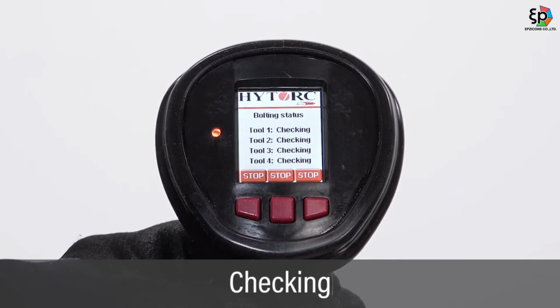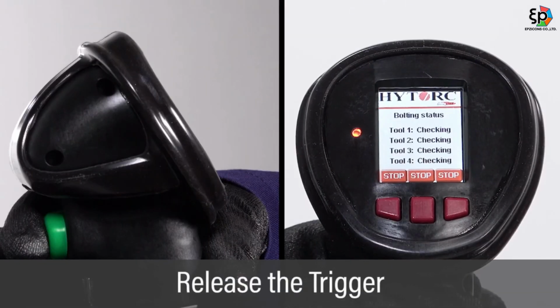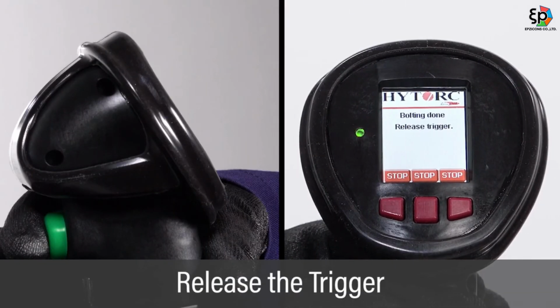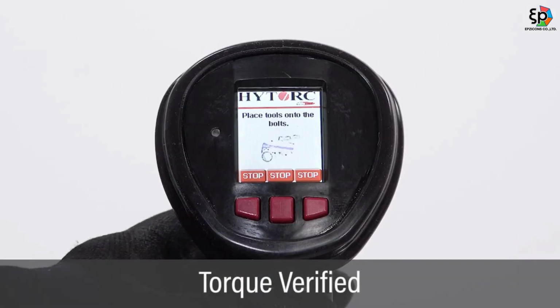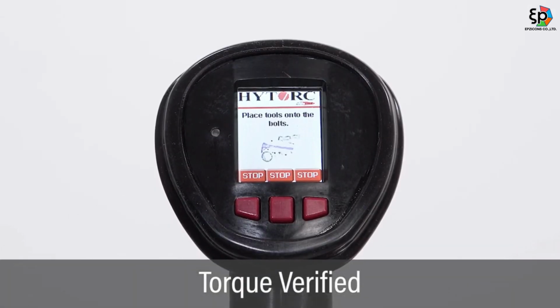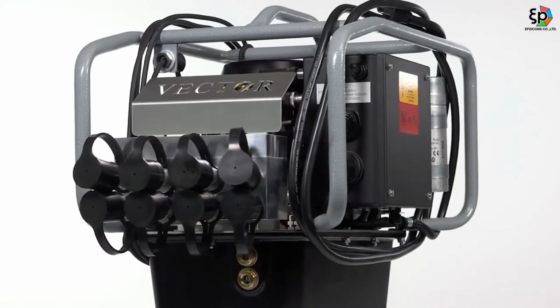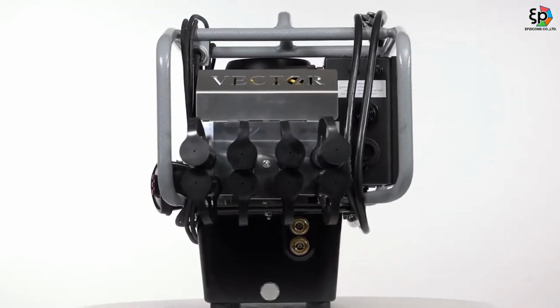Continue holding the green button as the pump checks the torque value has been reached. When the pump is done verifying the torque value, release the green trigger button. This completes the fully automatic torquing operation and verification. The vector pump can now be set up for the next bolting operation.